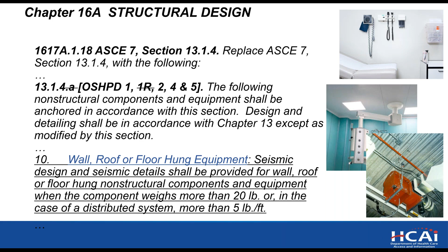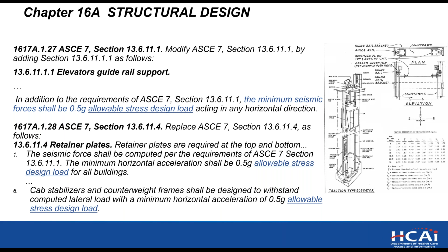Okay, so this is for design of elevator guide rail supports and retainer plates. Now, when they switched from allowable stress design to strength design in the building code, the minimum requirement for design of your elevator guide rail supports was based on 0.5 G. The maximum seismic force, 0.5 G, was the minimum that you had to design your elevator guide rail supports and retainer plates for. But by transferring from allowable stress to strength design, that 0.5 G remained the same. So the force that was for allowable stress design was now being under-designed when you moved from allowable stress to strength design. So we just clarified that that value, the 0.5 G in the building code, is the allowable stress design load. So if you're doing strength design, then you need to amplify it by the appropriate factor. Next slide.